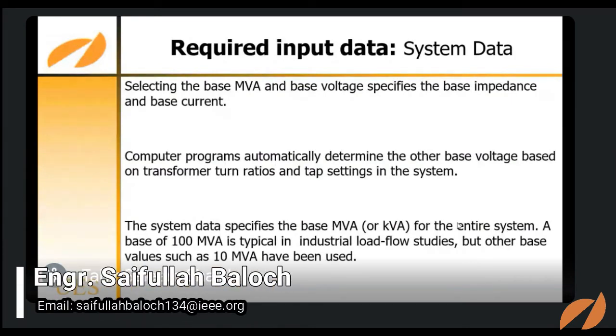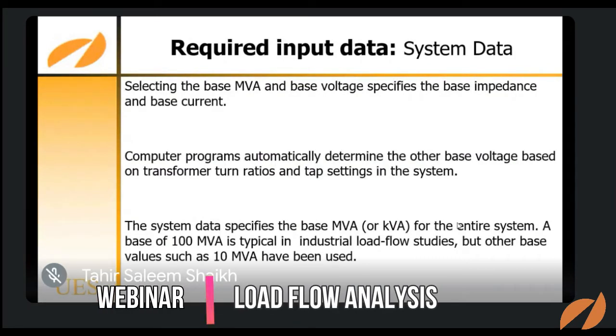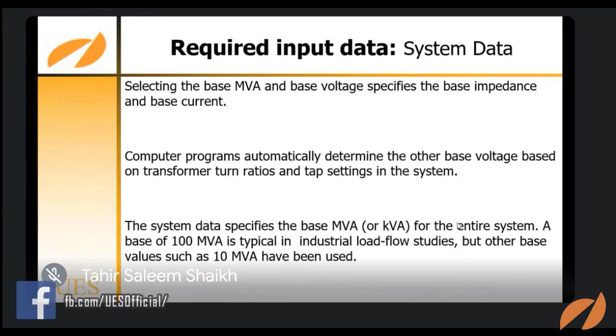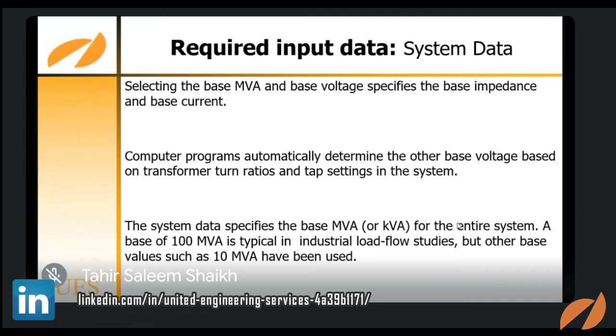Like in manual calculation, we used to select the highest value. That same procedure the computer also obeys: it uses that highest value as a base value for the system calculation. Like if there are 100 MVA, 10 MVA, 20 MVA, these are the different power ratings given on the different parts or components of the system. It will automatically select 100 MVA as the base MVA.